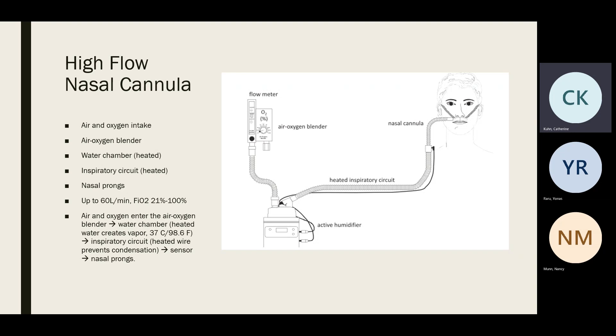The air is heated and a vapor is created — generally heated to 37 degrees Celsius (98.6°F). This vapor is transferred to the heated inspiratory circuit, which has a wire to continuously heat it and prevent condensation from building up. It goes through a temperature sensor and is then delivered to the patient via the nasal prongs.